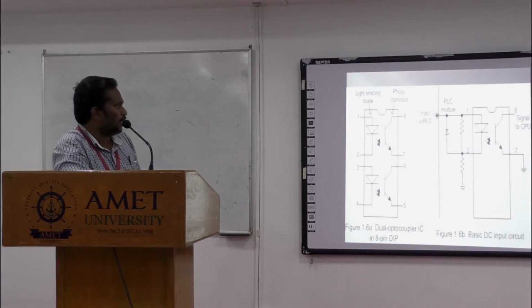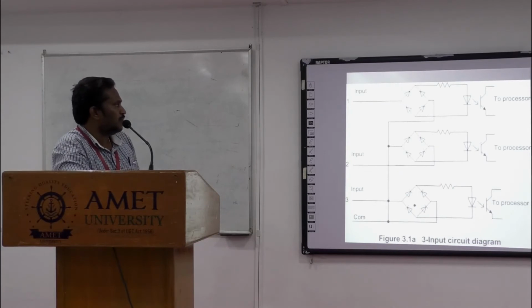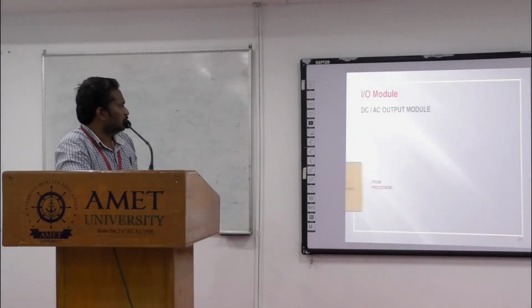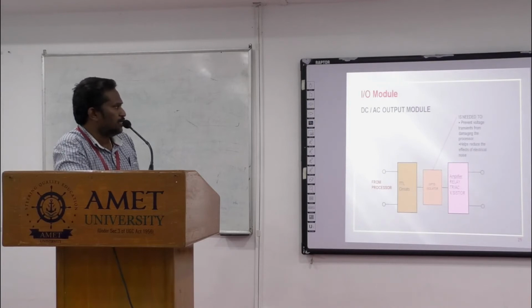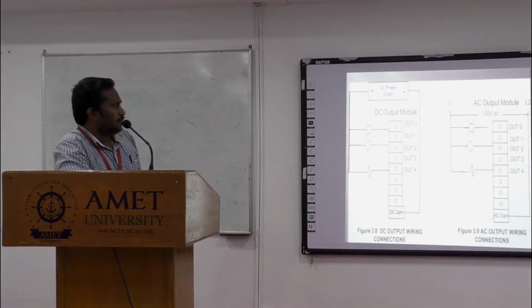So this is the opto isolator unit, which will have a light emitting diode and a phototransistor. The light emitting diode will emit the light. The phototransistor will convert the light into usable DC voltage. So this is the compartment which is inside the input module. The input module will have a number of terminals, and each terminal will have this compartment. DC and AC output modules are both combined in one single module. So this is the DC output module and AC output module. Same as the input module, the output module also will have a number of terminals, and it will convert the CPU DC voltage into usable AC or DC output voltage.